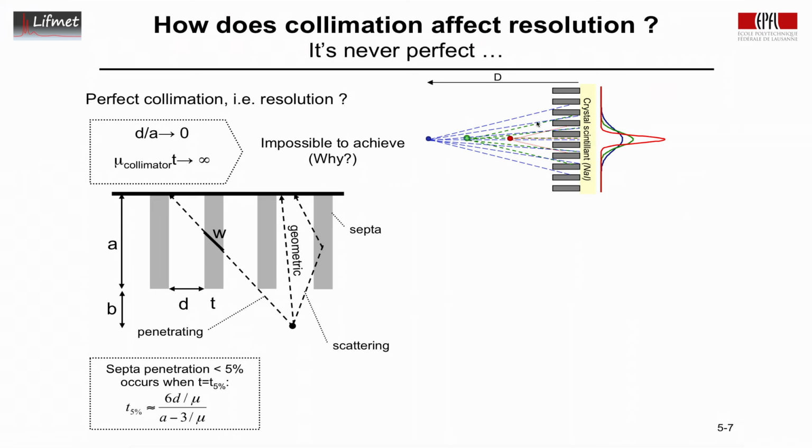A wider distribution because the geometric requirement is relaxed. We're further away, so we're increasing the probability that some X-rays will actually pass into the next bin on the side. And finally, for the blue object, we are even further away, and so its distribution, its width, as it's being detected, increases. That's another way of saying that the resolution decreases because the object is no longer represented by a point object.